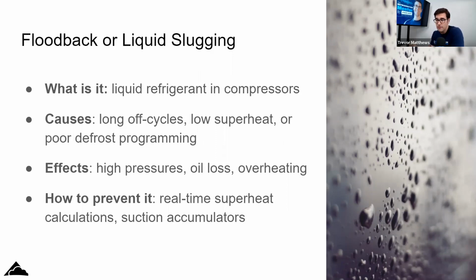It's airflow. If you don't have airflow, the temperature of that evaporator coil drops right off, and then you start to get liquid going back. But another big one is electronic valves. We're going to see more electronic valves coming out, and I'm seeing them in synthetic refrigeration. It's the only thing you use in CO2 refrigeration, and you can tell the superheat on every single case, every single box, and monitor that stuff, and it's all done through analytics.